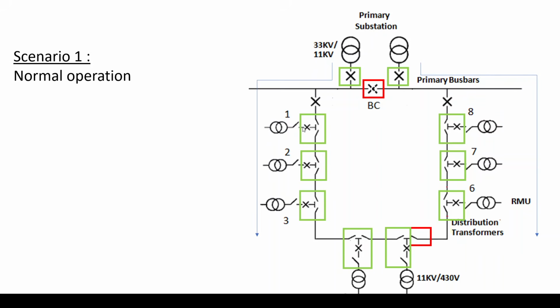So connected to each RMU, you can see here is a downstream distribution transformer. Then all these are LV loads, let's say. So this is a distribution. Let's say in this case, we are talking about a certain case, 33 over 11 kV. Then the ring is 11 kV, as is the case in several projects. Then the downstream here, let's say this is an 11 over 0.4 kV, and connecting this project, the same here, the same here. So in a scenario 1, let's call it normal operation scenario.